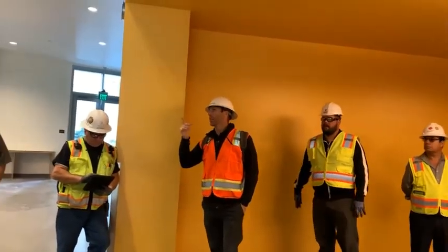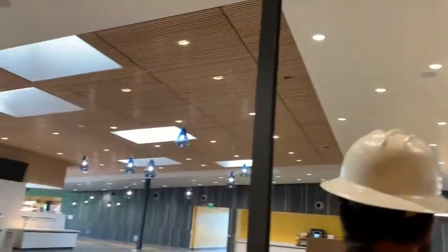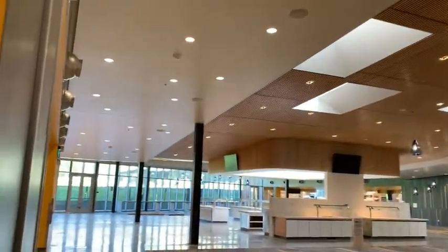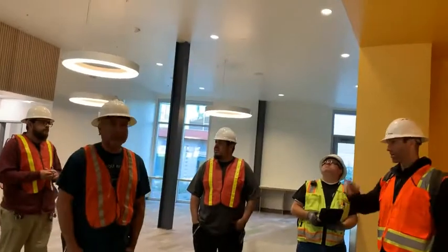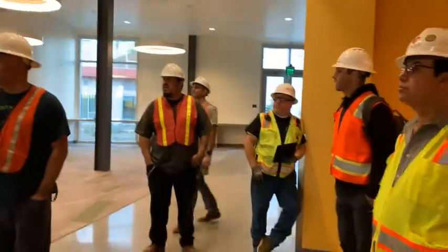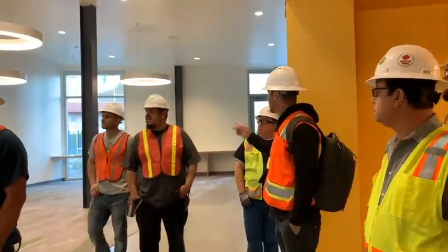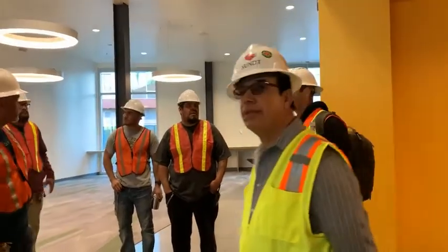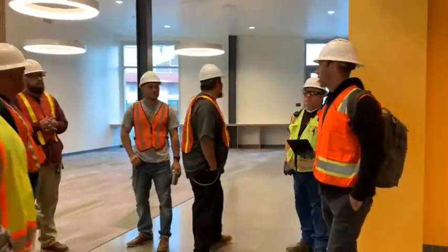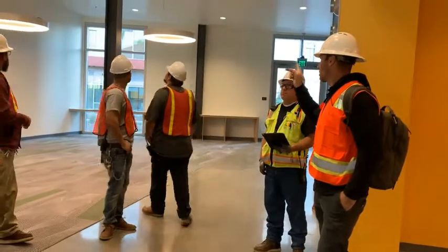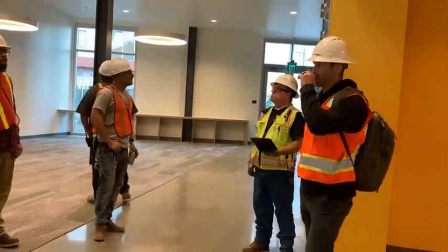The cafeteria itself is on a time schedule. So that doesn't have any aux sensors you can see. You'll see a photo cell from time to time. I see one down by the skylights. Probably get one over here by these lights. But most of these areas probably won't get much dimming on this side. Those windows aren't very big, and you have a big building right next to them.